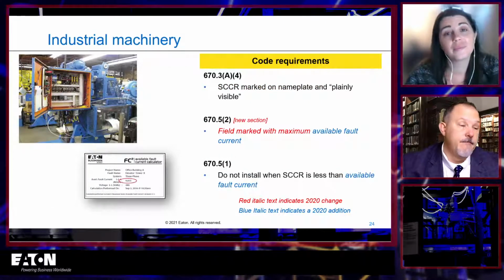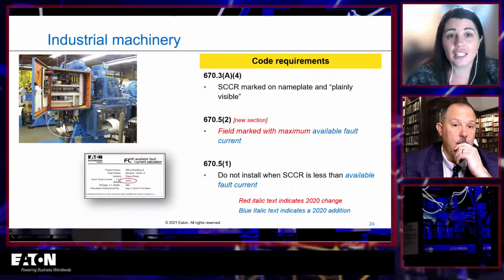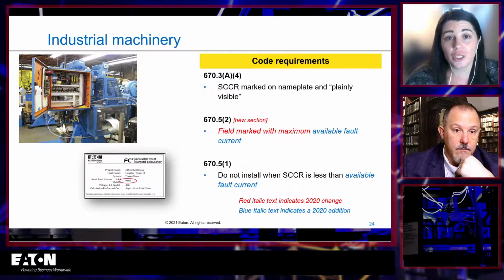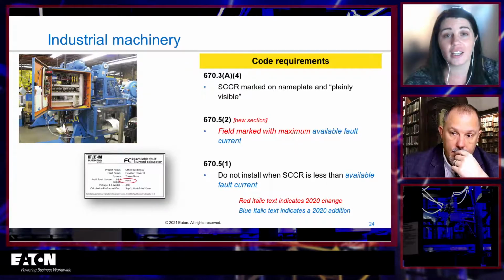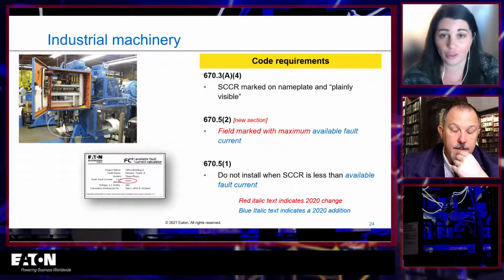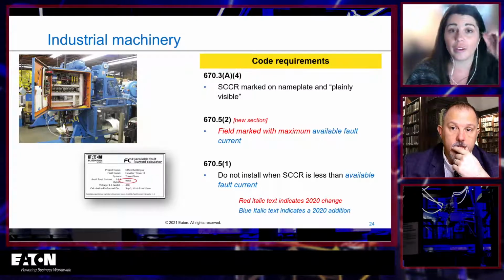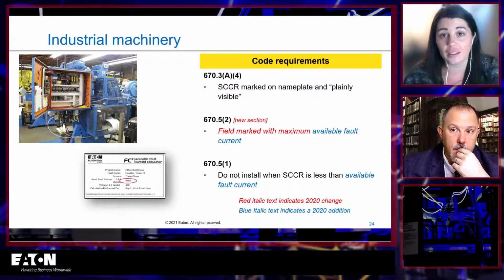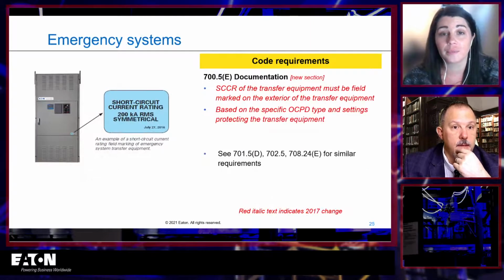It can be, yeah. And then last but not least, for industrial machinery in Article 670, SCCR marked on the nameplate, field mark again with the available fault current here. Don't install where the SCCR is less than the available fault current. So just another piece of equipment that this applies to.